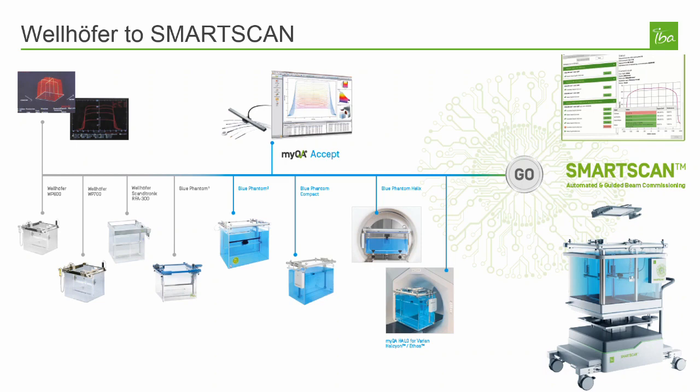SmartScan is a two-part solution comprised of the SmartScan Water Phantom and SmartScan software. The SmartScan hardware is the result of developments built on the well-known Wellhöfer and Blue Phantom line of water phantoms. SmartScan benefits from all those features but additionally offers automation that saves time and helps ensure the quality of the scanning process. The Stealth Reference Chamber saves time by removing the need for frequent chamber repositioning and provides an excellent reproducible signal quality even for SRS and SBRT fields.